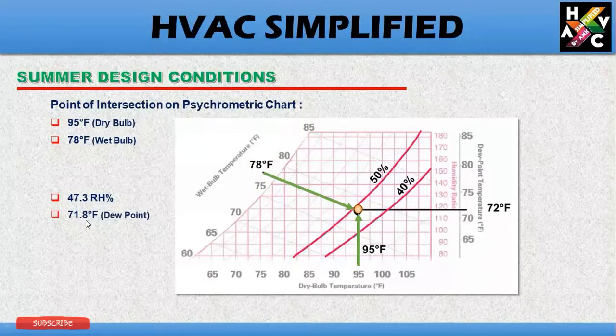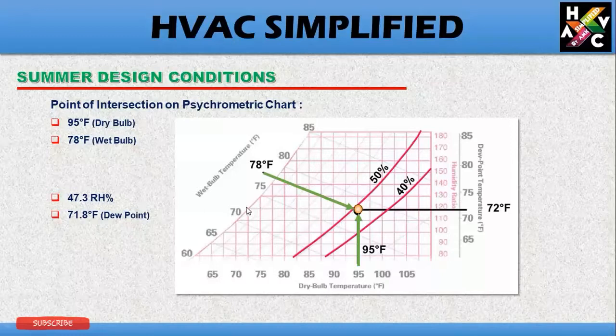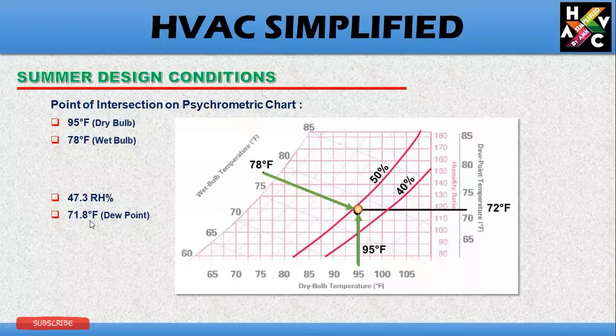71.8°F is your dew point. When you go to the left-hand side, this is your absolute humidity or dew point temperature, which means at 71.8 degrees Fahrenheit the condensation will start.